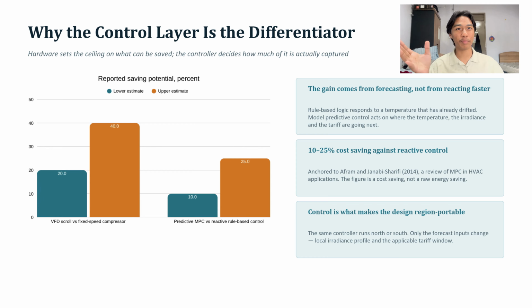A variable speed compressor gets up to 20 to 40% over a fixed speed unit purely from the hardware itself. But the bigger opportunity sits on top of that: predictive control against reactive control, which gives another 10 to 25% in cost savings. That figure comes from Afram and Janabi-Sharifi's 2014 research on MPC in HVAC applications. I want to be precise about this: it's a cost saving, not an energy saving, because those two are different things.